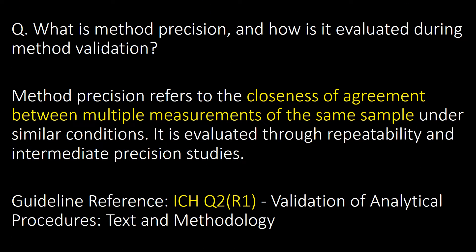What is method precision and how is it evaluated during method validation? Method precision refers to the closeness of agreement between multiple measurements of the same sample under similar conditions. It is evaluated through repeatability and intermediate precision studies. Guideline reference: ICH Q2.